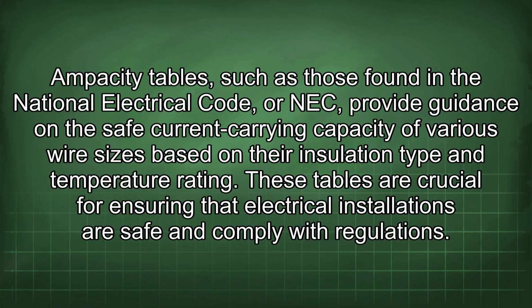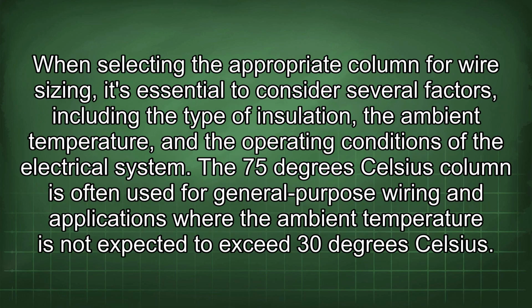Ampacity tables, such as those found in the National Electrical Code, or NEC, provide guidance on the safe current carrying capacity of various wire sizes based on their insulation type and temperature rating. These tables are crucial for ensuring that electrical installations are safe and comply with regulations. When selecting the appropriate column for wire sizing, it's essential to consider several factors, including the type of insulation, the ambient temperature, and the operating conditions of the electrical system.